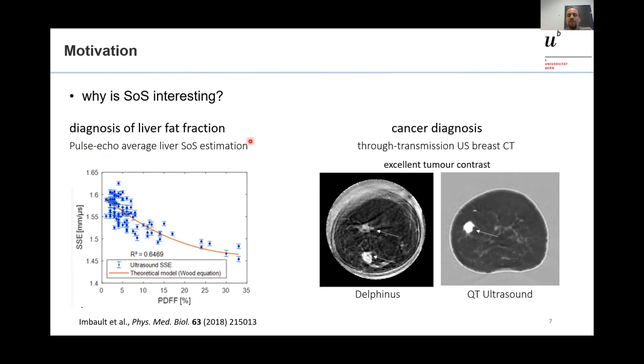On the other hand, we have ultrasound tomography, mostly promoted for cancer diagnosis. Similar to X-ray computed tomography, it is based on through transmission of ultrasound: we insonify on one side of the breast, detect on the other side, and rotate around the breast to reconstruct the speed of sound. There are two very good systems — one from Delphinus and one from QT Ultrasound — which show marvelous, exceptional contrast for breast cancer.